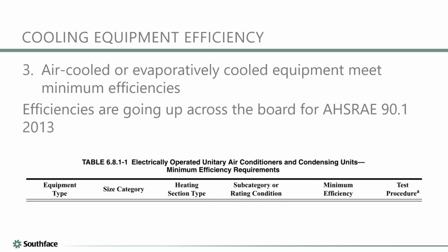So we can move on to the cooling equipment efficiency. This again is pretty straightforward. Basically, to comply with a simplified approach, your equipment needs to be able to meet certain efficiency requirements. They are in the tables here in the ASHRAE code manual. But one thing to point out, since we are talking about the new codes, is that efficiencies have gone up across the board for ASHRAE 2013. So if you're used to working with an older code, you might be used to speccing out the same HVAC equipment that you have for many years at this point. Just know that you need to look at some more efficient equipment, in general, and especially if you're going to be meeting the simplified compliance approach.